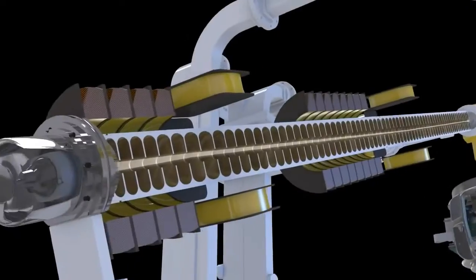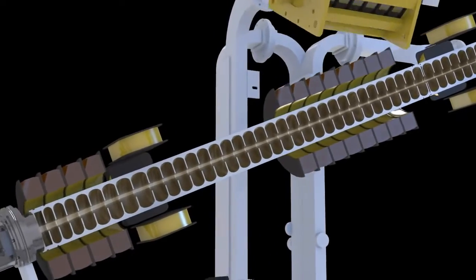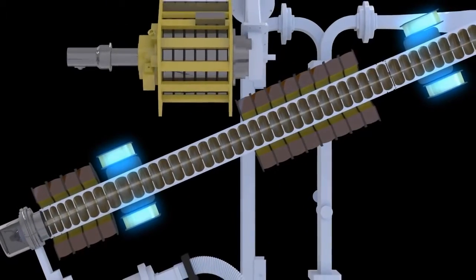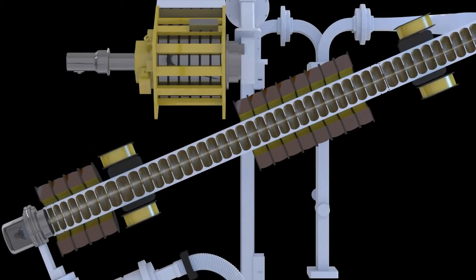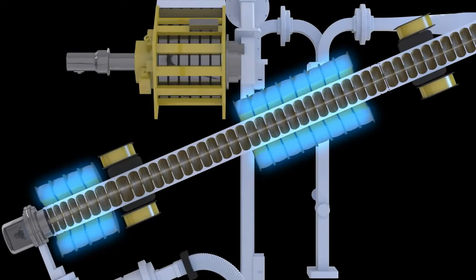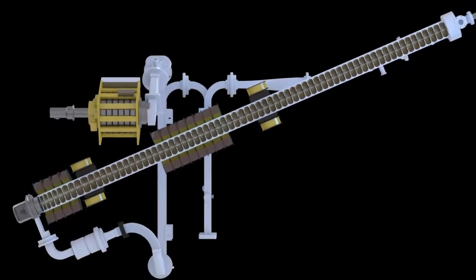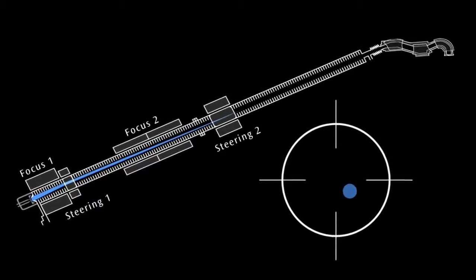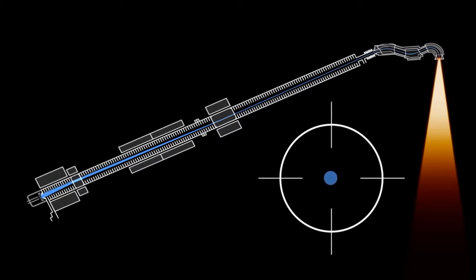The path of the negatively charged electron beam is controlled by two sets of quadrupole magnets, called steering coils, that surround the waveguide. An additional two sets of focusing coils help to further define the electron beam, so that it is very fine, with a diameter similar to that of a pinhead, when it hits the target.